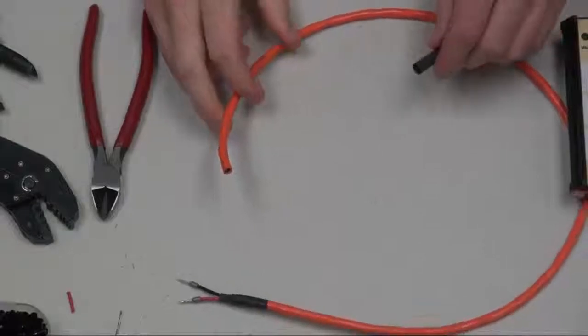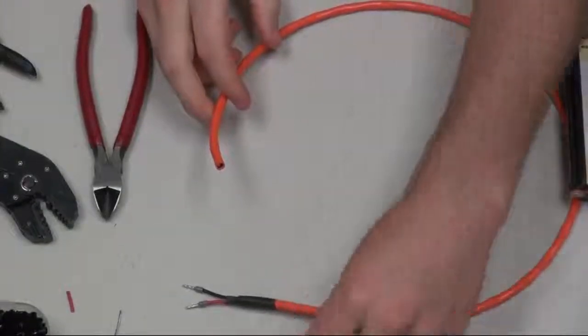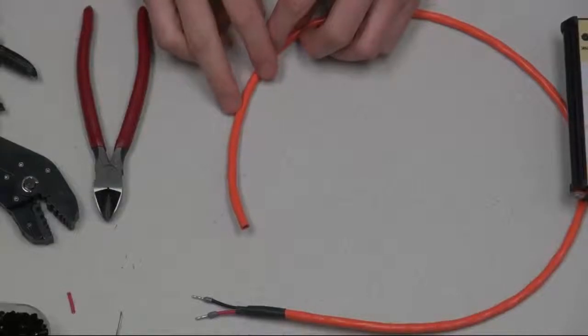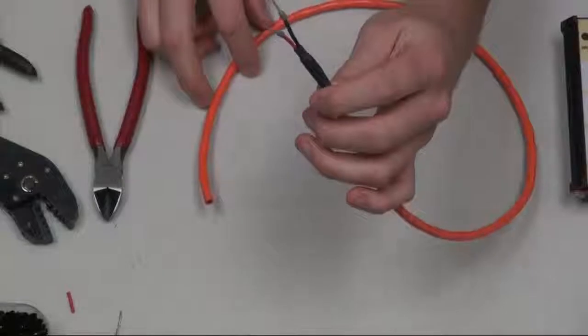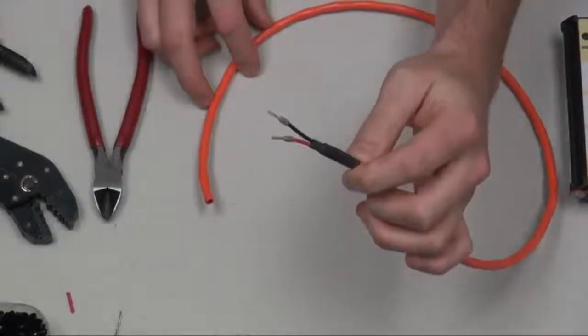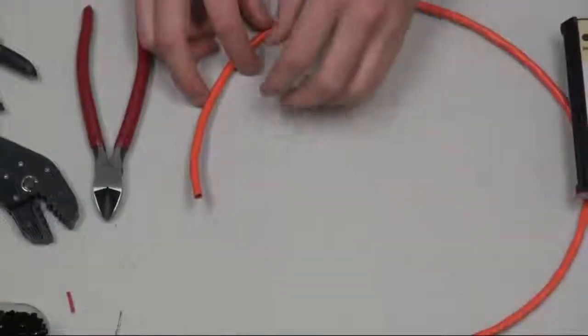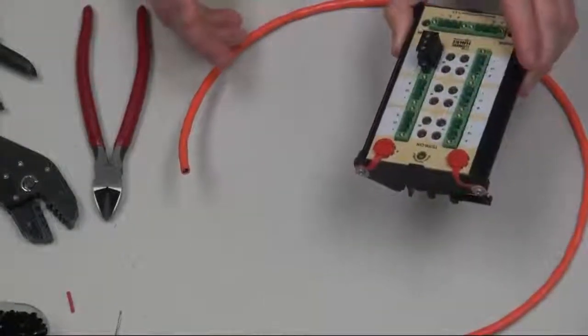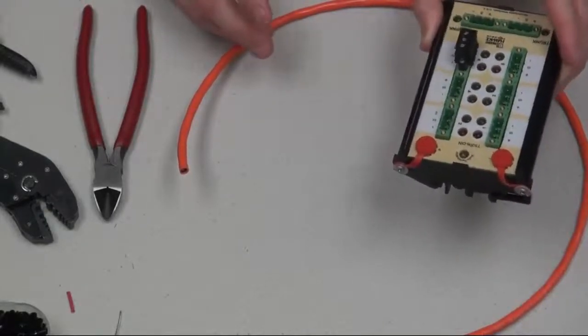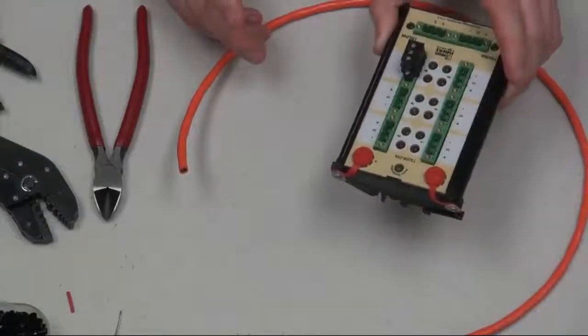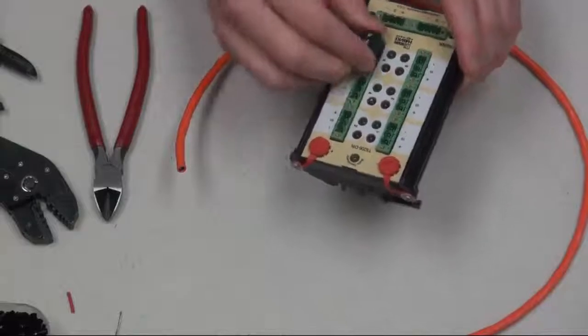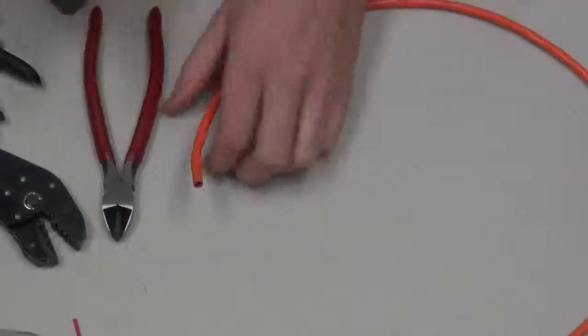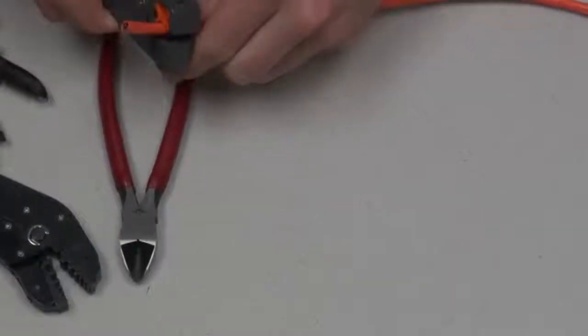Okay, what I want to also do here real quick is to show everybody how to actually do a similar thing with the wires where I'll strip and shrink and ferrule the wire, but in this case, instead of doing the two wires that you would connect to a device out in the field using single-point grounding, I'm actually going to do a similar thing, except this time we're going to connect it back to a coupler. So let me run through that process again for you guys. I'll go through it a bit quicker here since you've seen it once already.